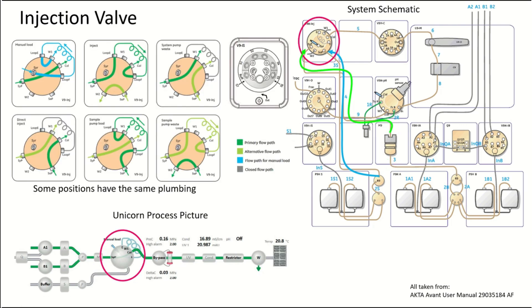Okay, so the injection valve has six different positions, but some of those positions have the same plumbing. You can see the system pump waste and the direct inject positions are the exact same, same with inject and sample pump waste. The default position, manual load, does not allow you to run the sample pump and the system pump at the same time. Other positions like sample pump waste will allow you to run them both.